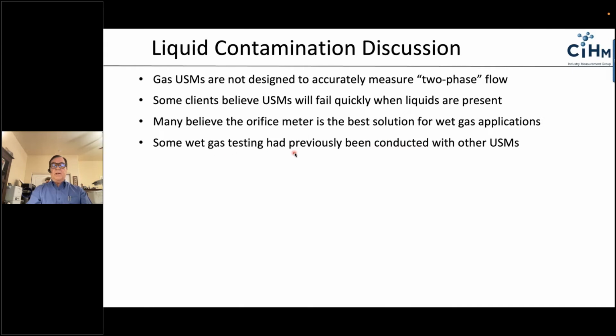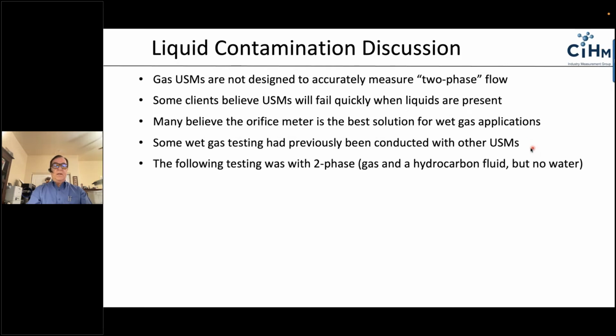Some wet gas testing has been previously done with other brands of ultrasonic meters at the CC Nunn facility. And we're talking about two-phase. And when I say two-phase, I mean, of course, natural gas and hydrocarbon fluid. It's a fluid that they use up there that's not as volatile as NGLs. It's called Exxsol D80, but not water. Most of the time in the wintertime, they don't run water through the multi-phase facility because of potential for freezing.